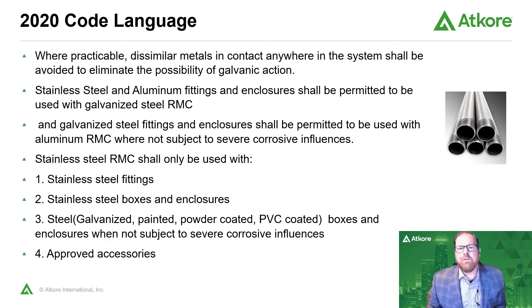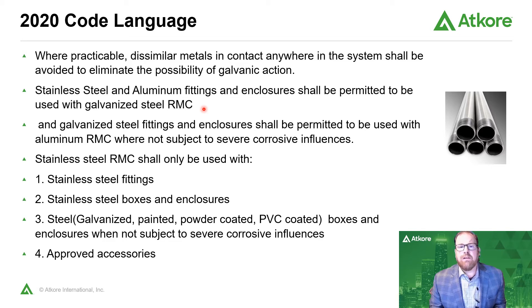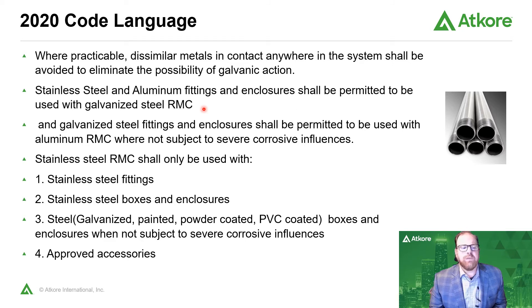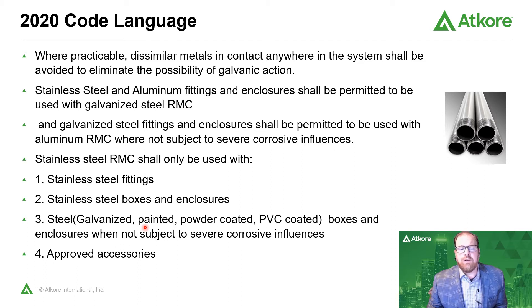Breaking down the 2020 code language: the second bullet says stainless steel and aluminum fittings and enclosures shall be permitted to be used with galvanized steel RMC. This puts in the missing piece from 2017 — you are allowed to use stainless steel fittings with galvanized rigid metal conduit, enabling that transition. So you can use stainless steel fittings with both stainless steel conduit and galvanized conduit. Additionally, stainless steel conduit can be used with any stainless steel fitting, any stainless steel box and enclosure, or a galvanized box or enclosure where not subject to severe corrosive influences.